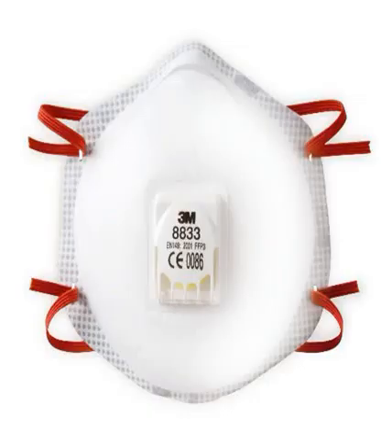For example, EN 149 FFP2 masks have similar performance requirements to N95 masks in the United States and KN95 filters of China, and EN 149 FFP3 masks have similar performance requirements to N99 masks in the United States. However, EN 149 test requirements differ somewhat from the US, Chinese and Japanese standards.